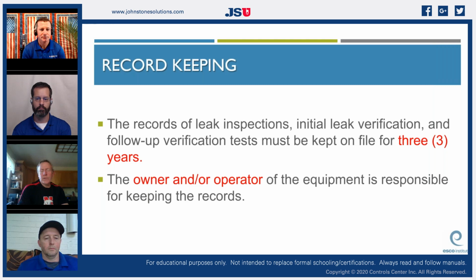This is good for all techs to know, whether they're residential or commercial, to keep records, initial leak verification, follow-up verification tests on file for 3 years. We did it even in residential. We put the amount, the type, and the address of every time we added refrigerant or removed refrigerant. You bet.